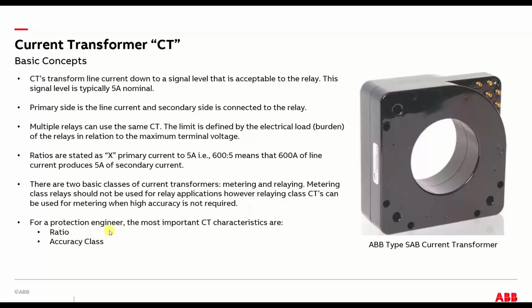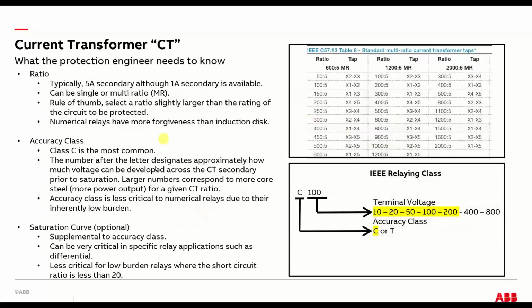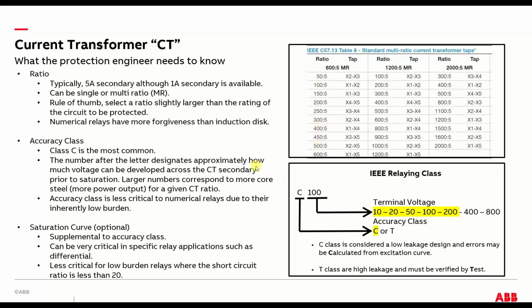So kind of the bottom line, and I'm going to move off the CTs as fast as I can because this just gets too deep. But from a protection engineer standpoint, the most important things to know about the CT are the ratio and the accuracy class. I'm going to try to go through some of this quickly. Here's a table of some standard CT ratios. These are for multi-tap CTs, so you can get a CT that you can reconfigure its ratio based on what taps and jumpers you put on it. So you can get a 600:5 MR, which would be multi-ratio, and that can be set to drive either a 50 amp load or a 600 amp load, and all these variations in between.